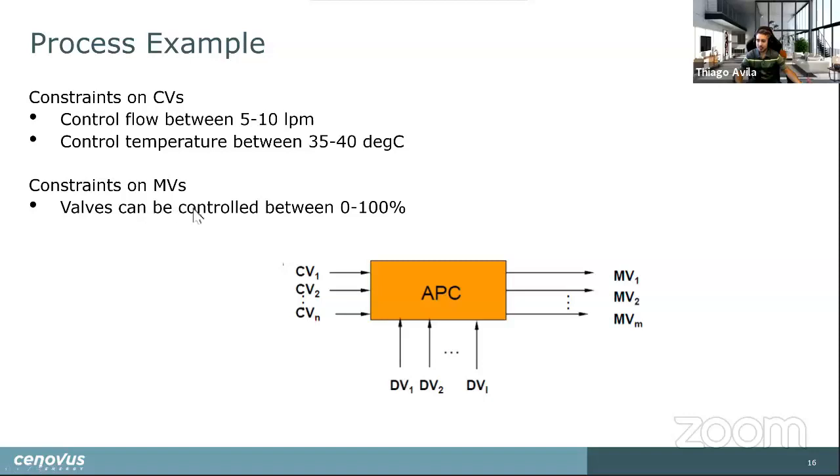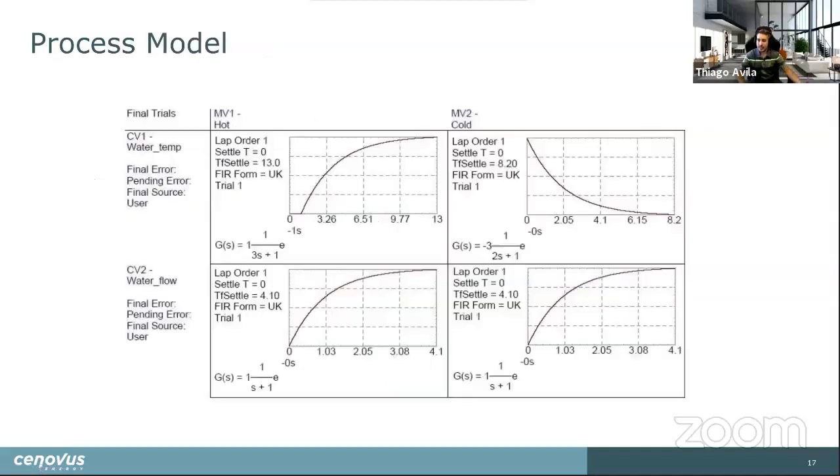So an example that's typically used in these APC explanations is a shower. You've got a pretty simple 2MV2CV system. Your two manipulated variables are the hot water and the cold water valve. And the controlled variables are the flow and temperature coming out of your shower head. So you'd end up with a two by two matrix in the APC controller. We'll set the flow between five and 10 liters per minute and the control temperature between 35 and 40 degrees. And the MVs, each valve can be open 0 to 100 percent. And if you step test your shower, you might end up with models that look like this. These are all Laplace transforms. The Laplace transform allows you to characterize the dead time, the dynamics of how long it takes to actually rise and react, and then the settling time.